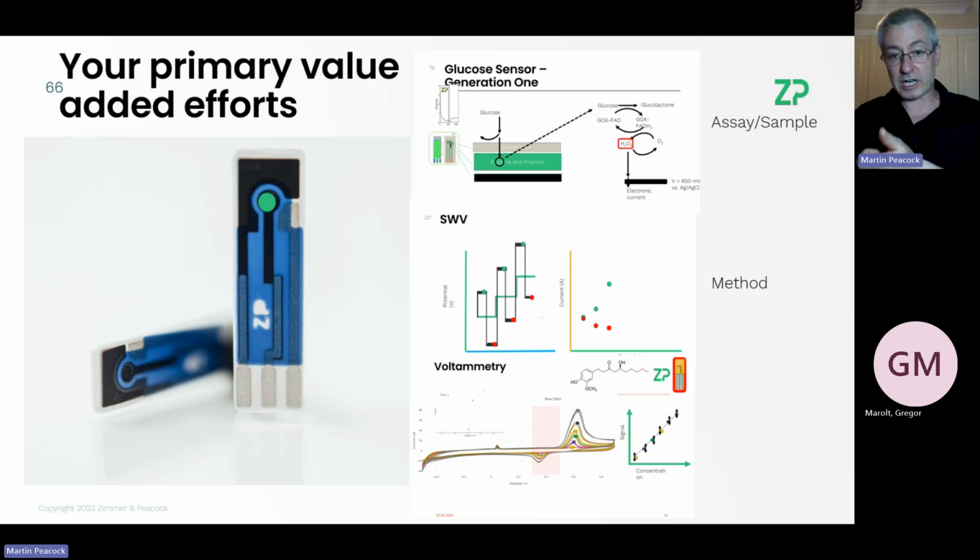I know it's not going to work terribly well because blood's a hard matrix, but working in that matrix and coming up with a routine to get the signal out of that total signal is a good place to spend your time. So that's essentially calibration. These are the three places, if you put effort in, that's where you add the most value. These are the patentable parts.